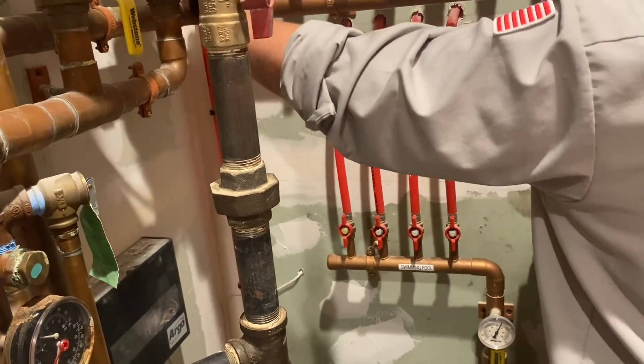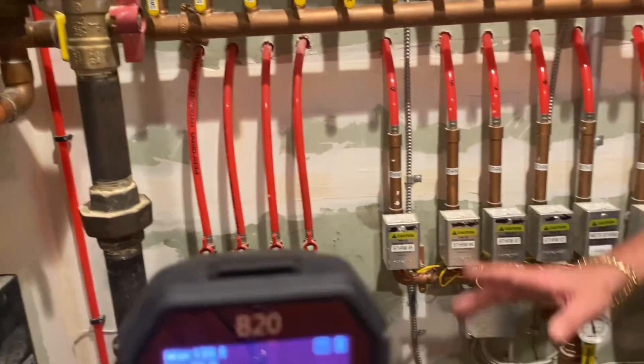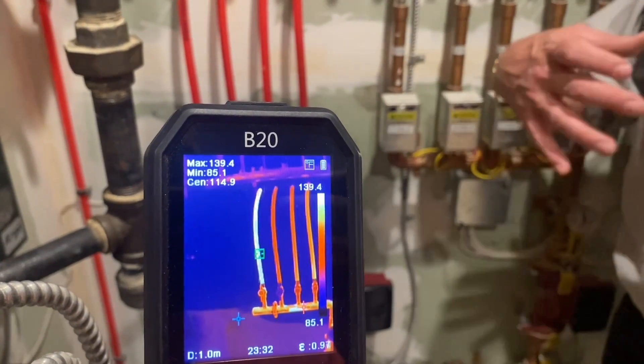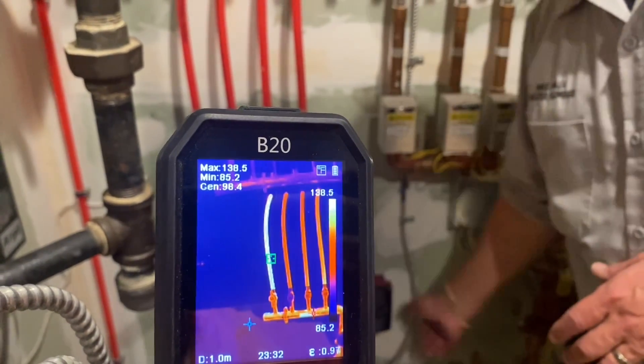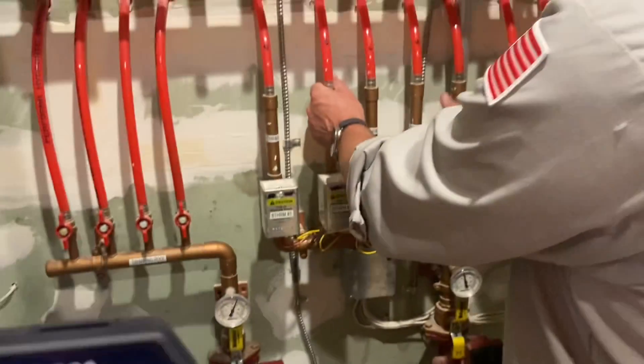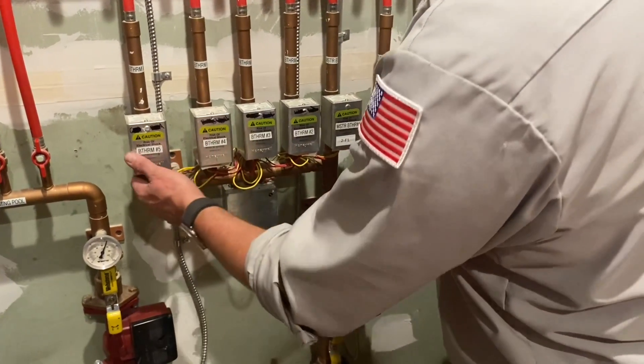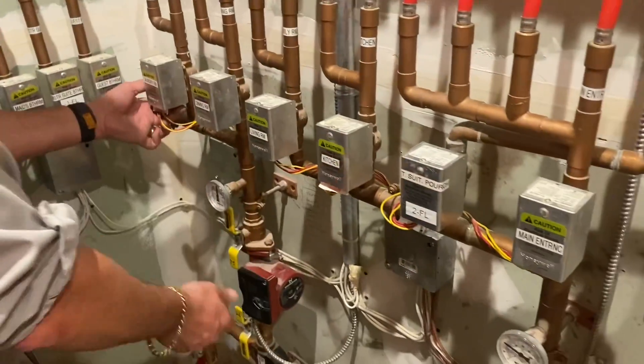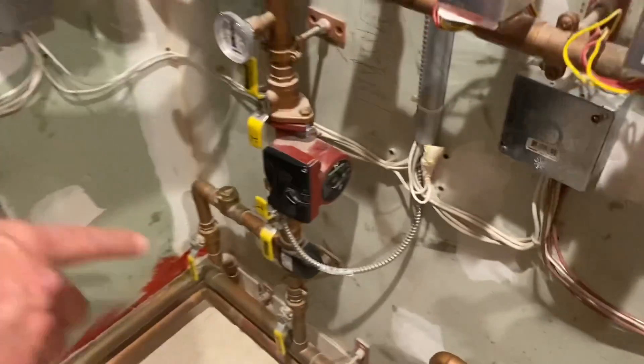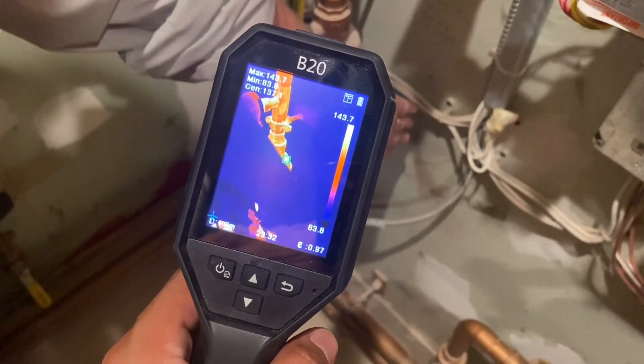Do that once or twice — open, closed, open. Now, it's going to be really early to tell, but if we take our thermal imaging camera to the floor in the pool room soon, if it's circulating, we should be able to see circulation down there. However, are these circulators on? No. Let's see. I have a good gut feeling about our gradient — this one's on.